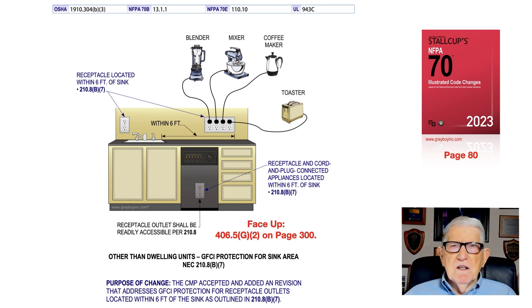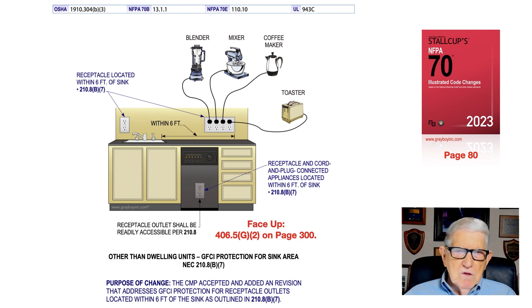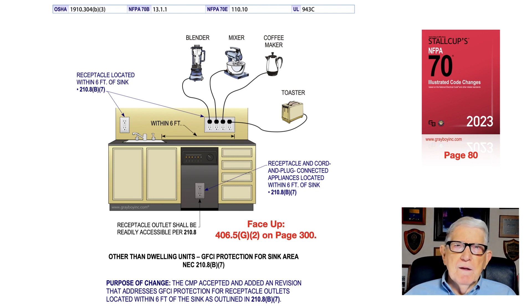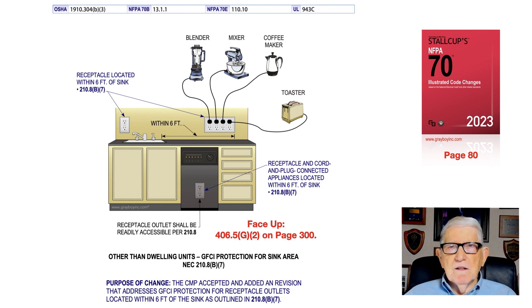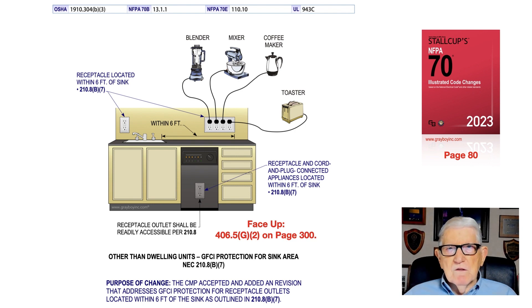On page 80 of the NEC, or in the Stallcup Illustrated Code Change book, this information is available. If a receptacle is not readily accessible, you could have a regular receptacle protected by a GFCI circuit breaker in the panelboard. The key point is that receptacles located within six feet of the inside wall of the sink require GFCI protection for personnel.